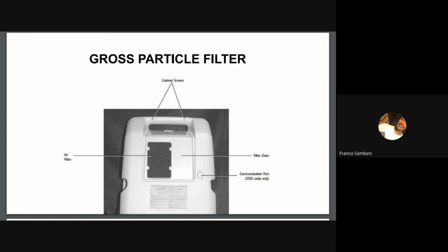But if you don't have that, you can use a piece of gauze. It doesn't have to be many pieces of gauze, just 2 or 3 is enough, just to make sure that it traps the dust. In extreme environments where you have a lot of dust in the area, if you use it with a filter, of course, but because the environment is extreme or harsh, the bacterial filter, the air intake filter inside, will prematurely occlude, causing a decrease in the performance of the unit itself. So if you're in a harsh environment, you should make sure that you wash the gross particle filter almost every day. I guess in this case, it would be right to have a spare gross particle filter, so that while you're washing one, the other is in place of the dirty one.